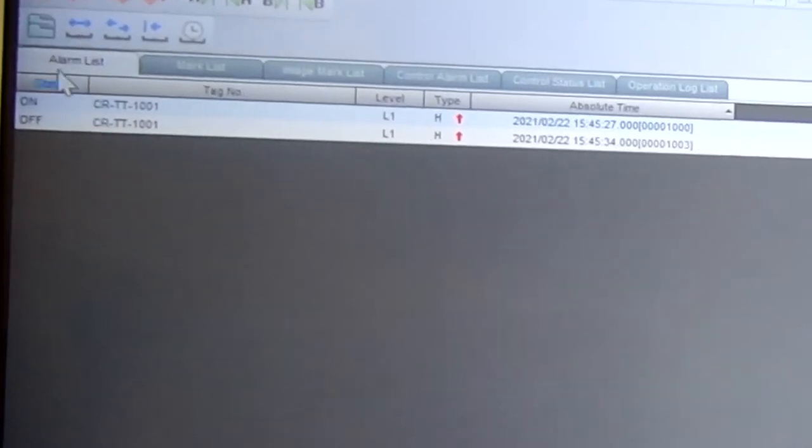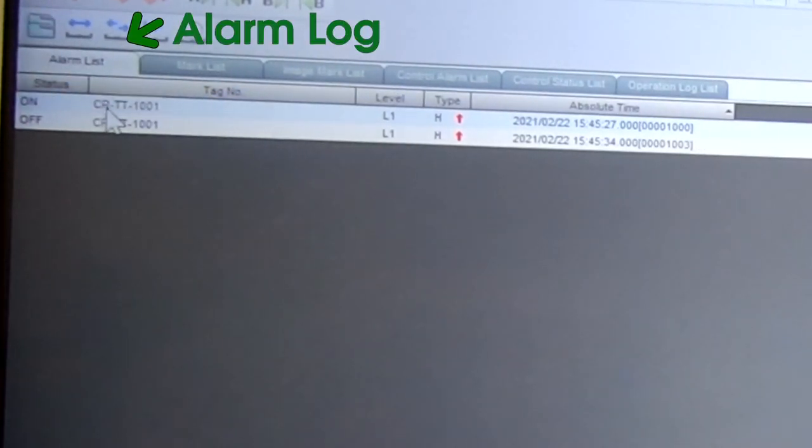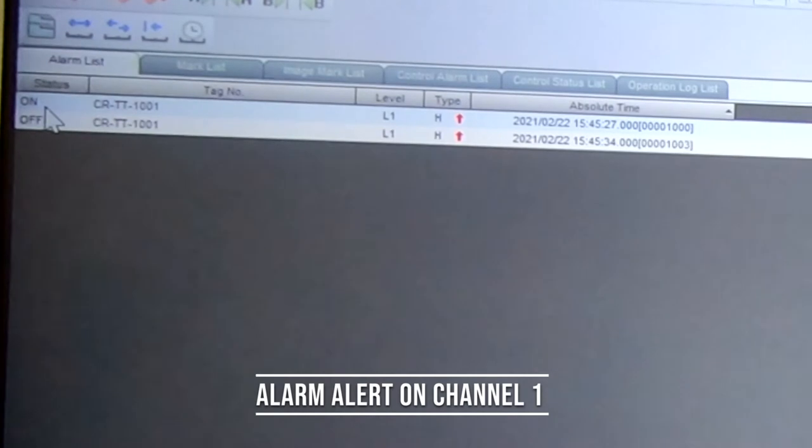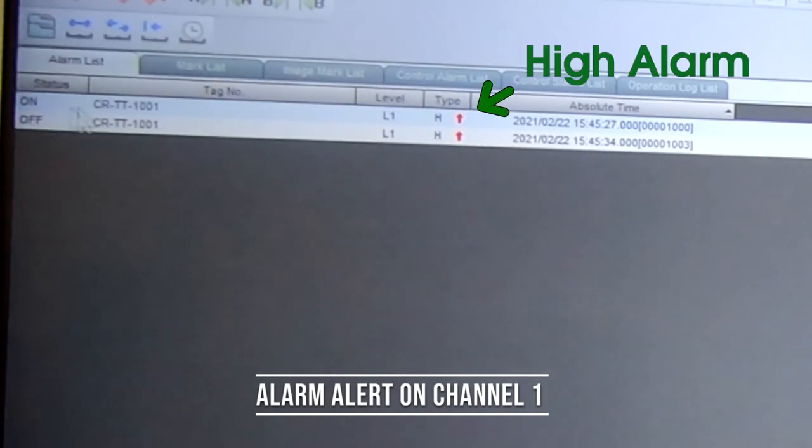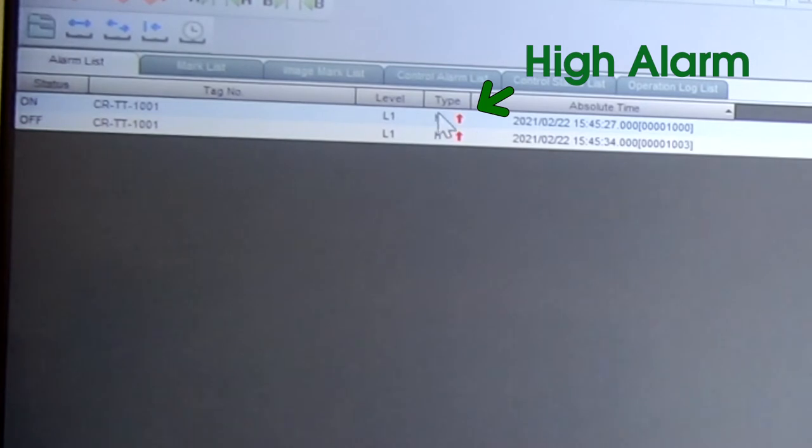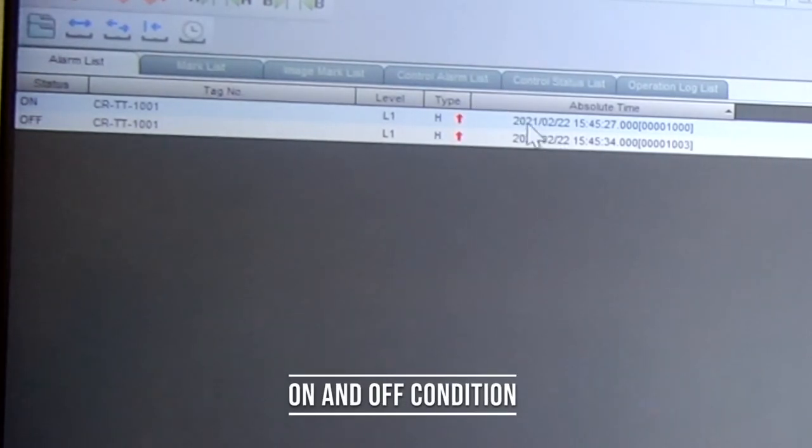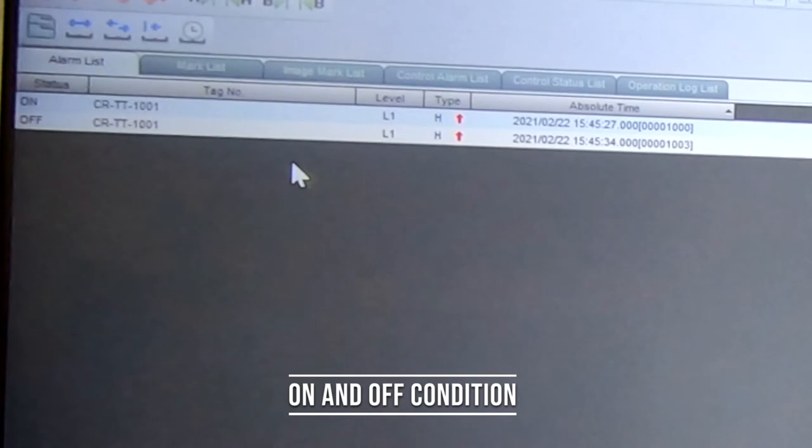When you go to list, you have a number of tabs starting off with the alarm log for any alarms that were generated. In that last video we had forced an alarm on channel one, which is a clean room temperature. We see it's a high alarm and it gives us both the on and off condition for that alarm.